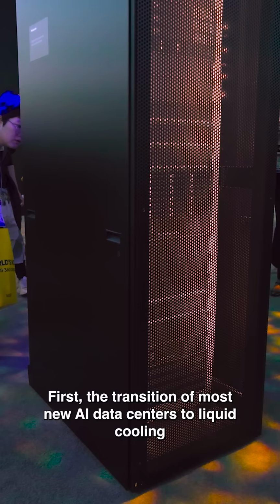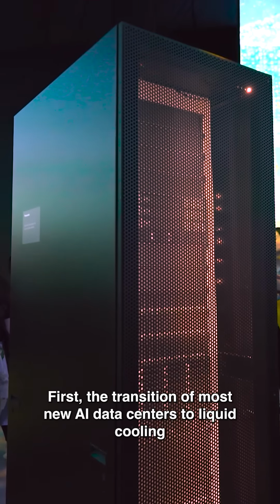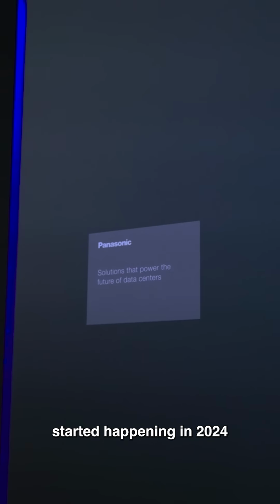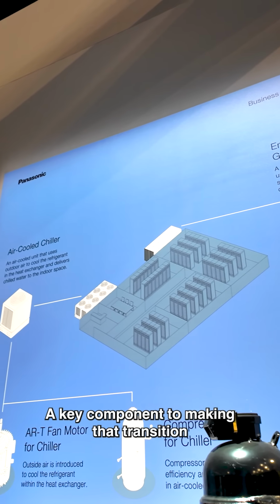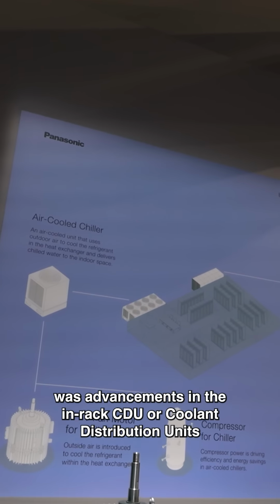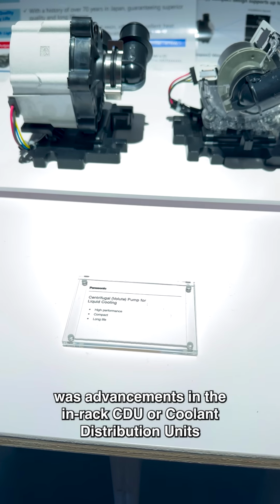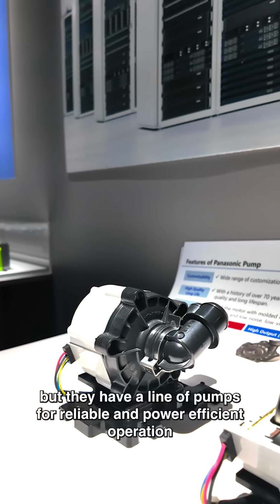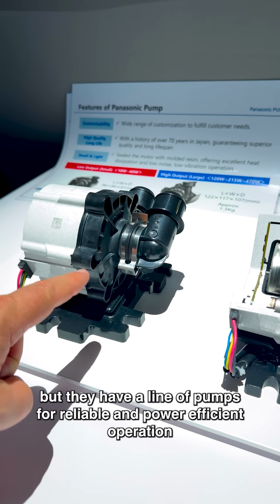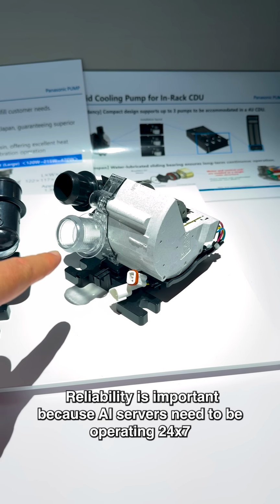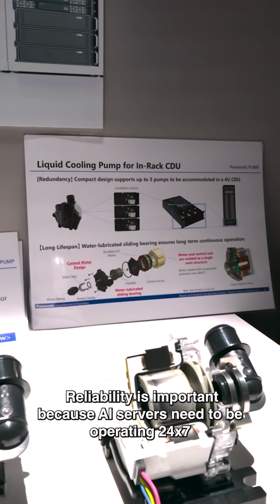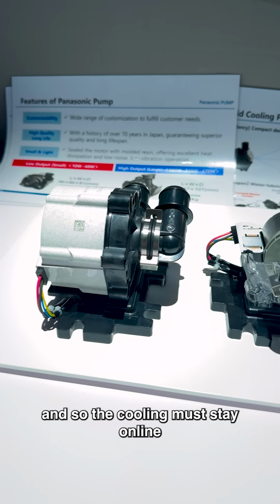The transition of most new AI data centers to liquid cooling started happening around 2024. A key component to making that transition was advancements in the in-rack CDU, or coolant distribution units. Panasonic doesn't make CDUs, but they have a line of pumps for reliable and power-efficient operation. Reliability is important because AI servers need to be operating 24/7, so the cooling must stay online.